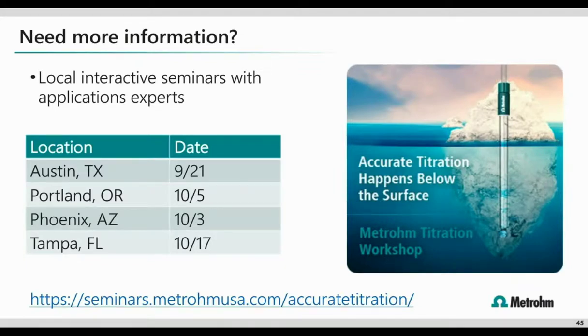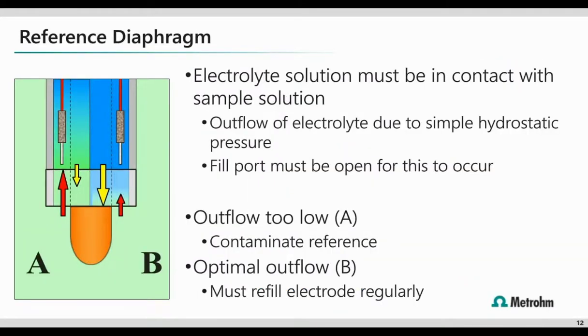Excellent. Now, what did you mean by the electrolyte level being too low? Do you mean below the sample level? Yeah, that's exactly right. I don't know if it's helpful to jump back out to that slide where we were having that discussion. So I believe this was the slide we were looking at. Yes, the image on the left in section A: once the electrode is submerged into the sample, that would mean the sample volume is actually higher than the electrolyte volume in the electrode. So you're on the right track with that. Definitely keep it filled higher to avoid that contamination.